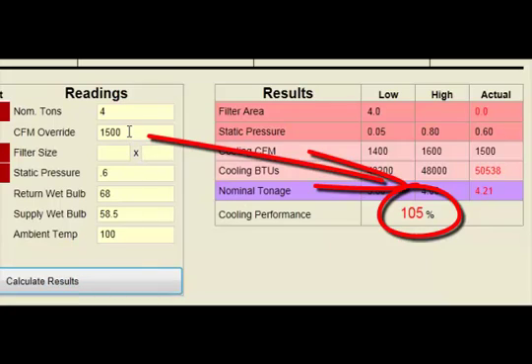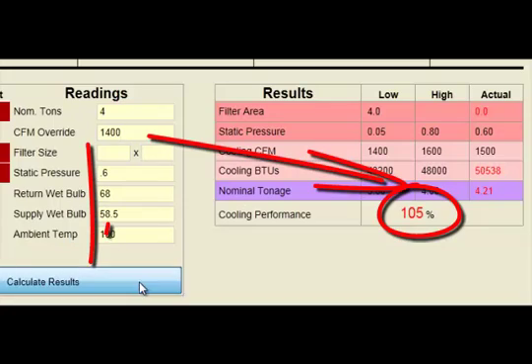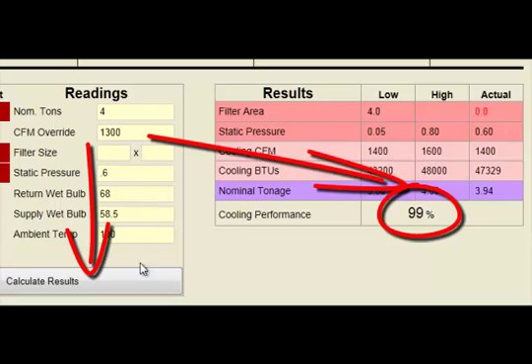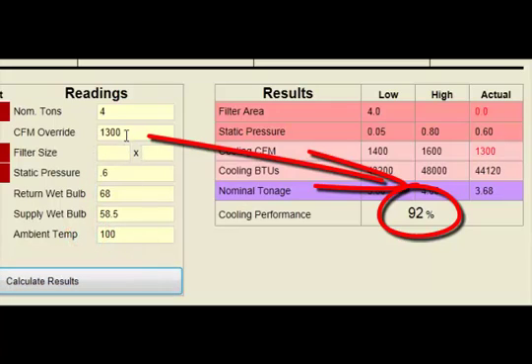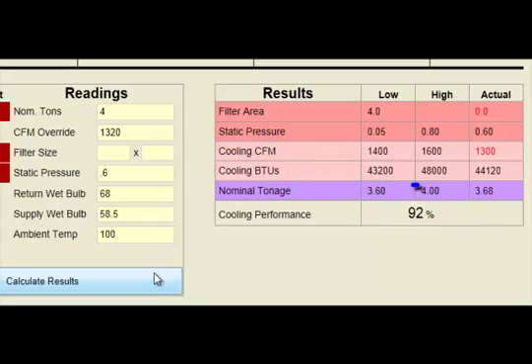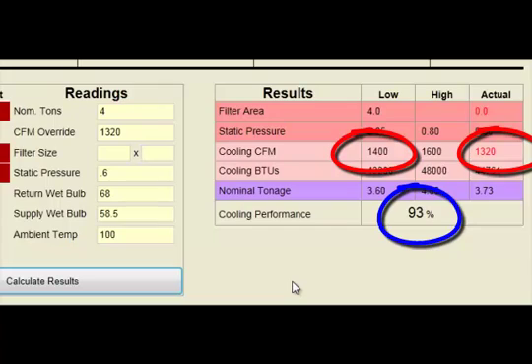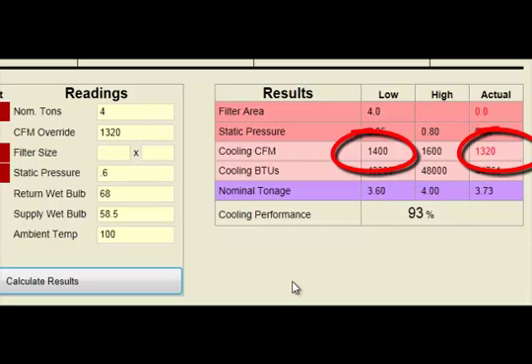By reducing the airflow number in the CFM Override field and recalculating the results until the system shows approximately 93% of system capacity, technicians can quickly estimate the system's actual CFM to determine if it's still within an acceptable range of operation.